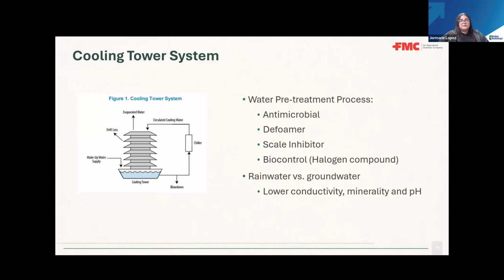As part of the project, the fresh makeup water that was previously extracted from the wells is now partly from the rainwater harvesting system. The rainwater is lower in conductivity, has fewer minerals and a lower pH compared to groundwater, and this reduces the scaling that could be formed due to these solids and mineral buildups. Next slide.